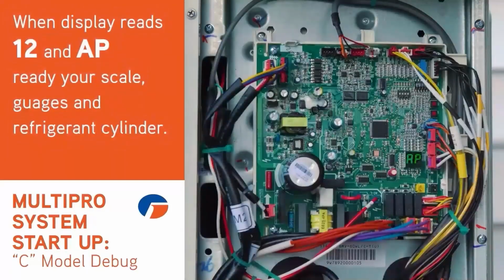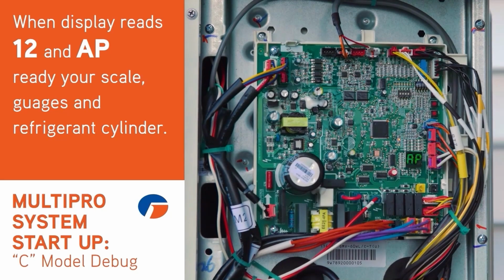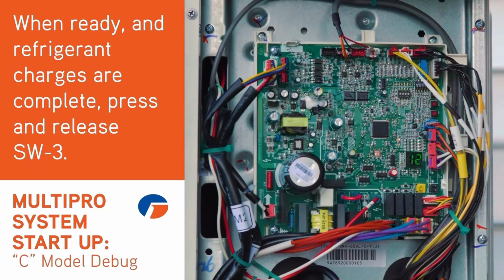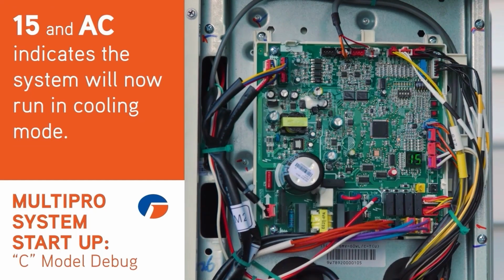When the display reads 12 and then AP and you needed to add remaining charge to the system, ready your scale, gauges, and refrigerant cylinder. If ready, or if no additional charge was needed, press and release SW3. The system will now display either 15 and then AC, meaning it will now run in cooling mode, or 16 and then AH, meaning that it will run in heating.